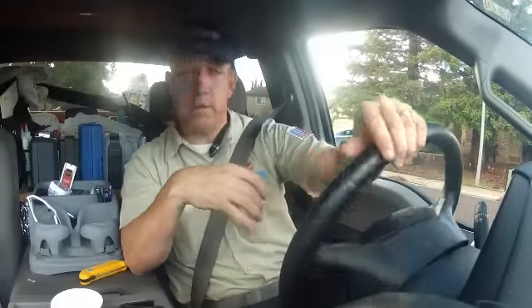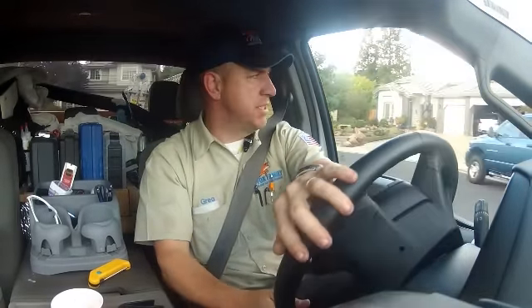Okay guys, well, we got that house up and running, so that was nice. And we did a little safety check of the heat exchanger as well. So yeah, basically that old zone board was set up in a way that you literally had to manually go up there and switch it from cool to heat. It would come on in heat, but zone 2 wouldn't work unless you had manually switched it over.